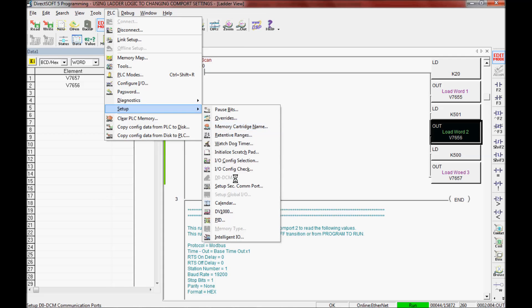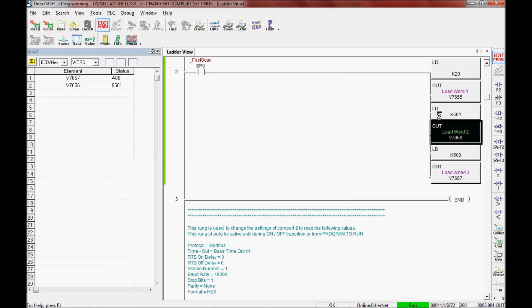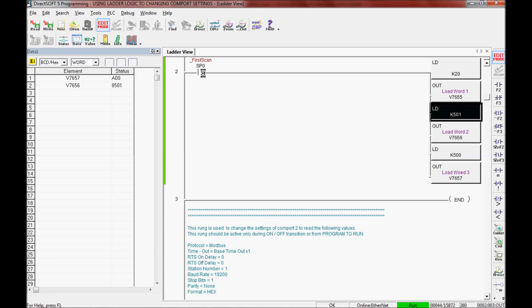That value of 8501 comes from all these options being checked — that's where the 8 comes from. The baud rate and parity are also changed; the parity has changed from none to odd. I'll click OK and close. Right now I'm going to write a value of K501 to word number 2. Since this bit is only active on the first scan, I need to either power cycle the PLC or transition from run mode to program mode and then back to run mode again.